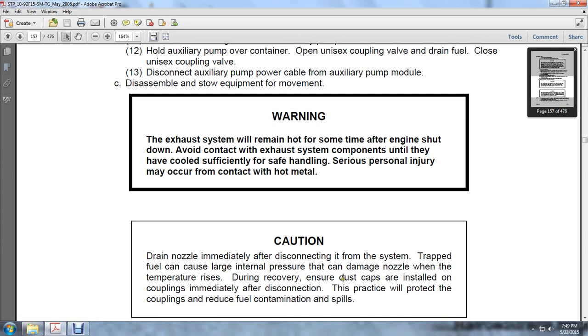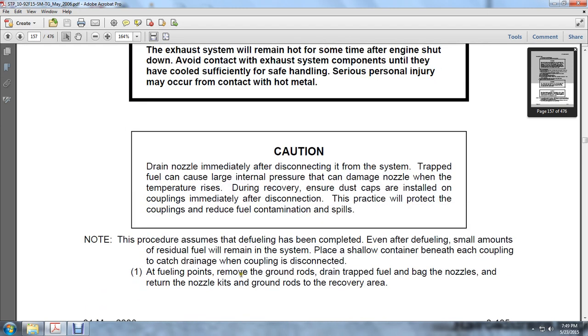During recovery, ensure that dust caps are installed on the couplings immediately after disconnection. These practices will protect the couplings and reduce fuel contamination and spills. This procedure assumes that defueling has been completed. After defueling, small amounts of residual fuel will remain in the system. Place a shallow container beneath each coupling to catch the drain where the coupling is disconnected.